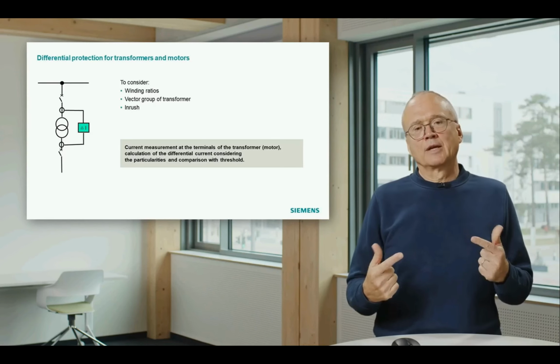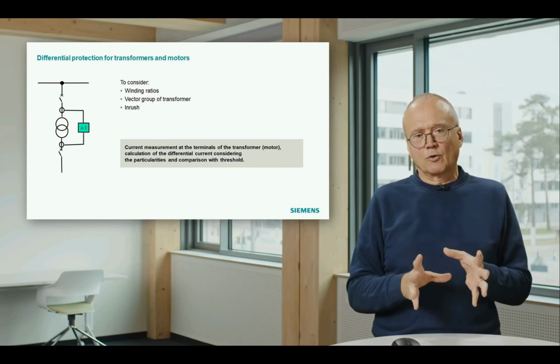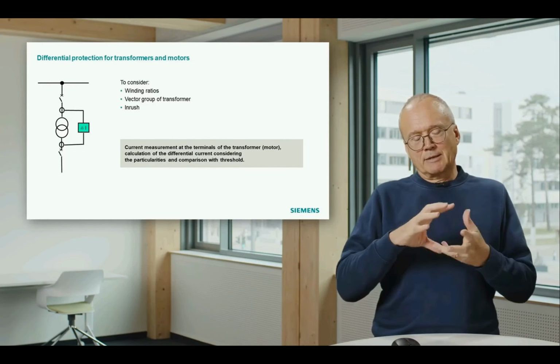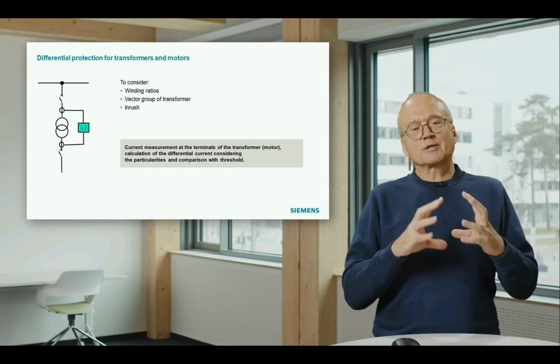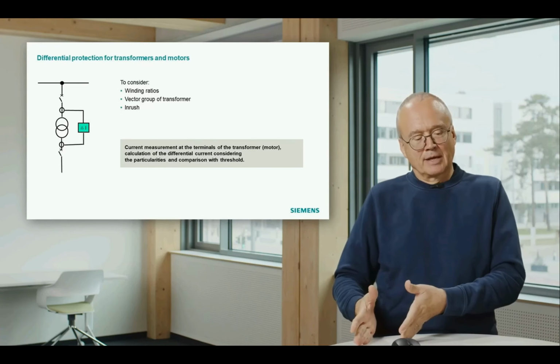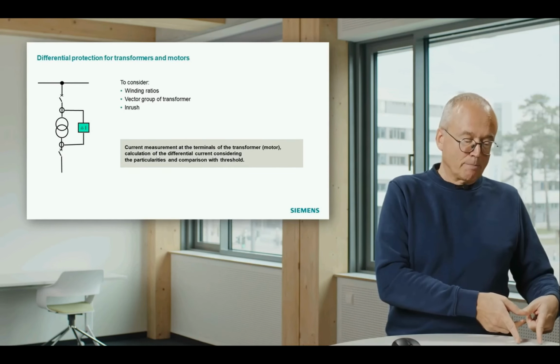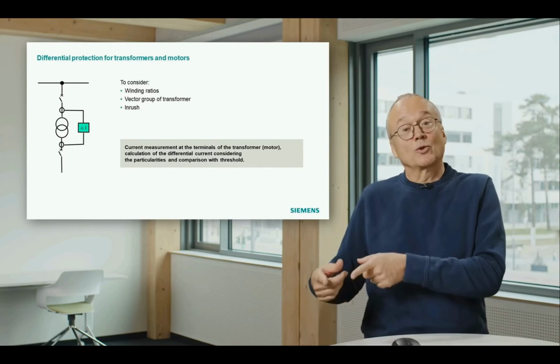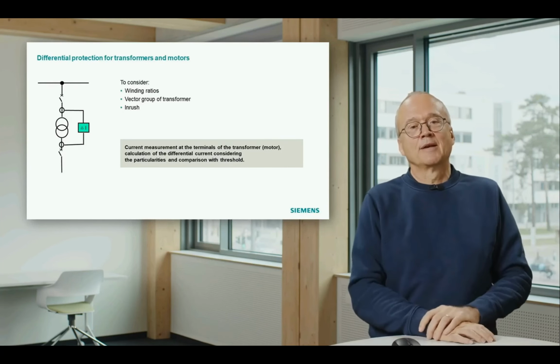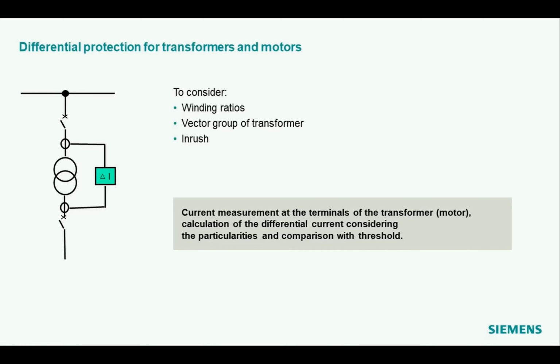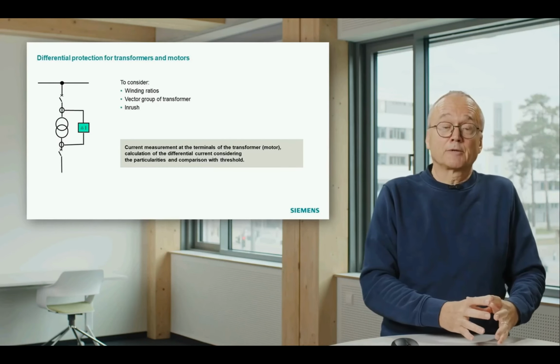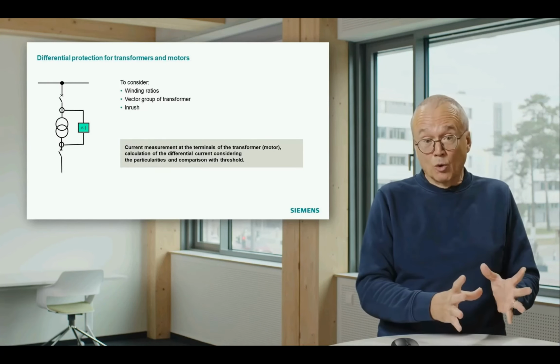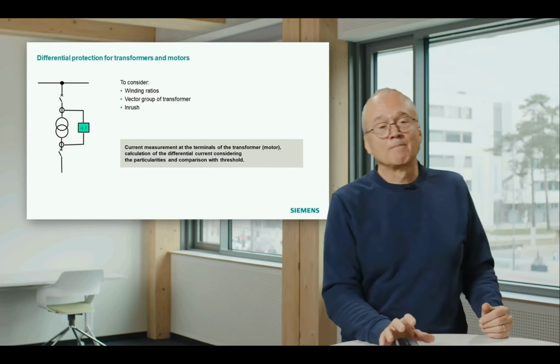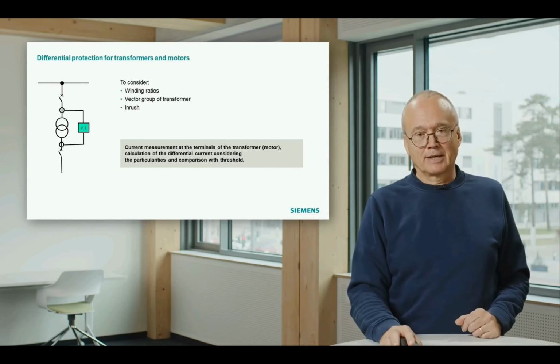And it's not only the ratio. If you look at a three-phase power transformer, that normally has, depending on the connection of the windings, a phase shift between one side and the other side. And that also means if we compare the current on one side to the current in the same phase on the other side, we must take into account this phase shift resulting from the connection of the windings. And we also have to think about what happens if we energize the transformer and we have an inrush there. That means the differential protection principle can be applied to transformers, also to motors and generators, but we have to take into account a few things to make it applicable in reality.